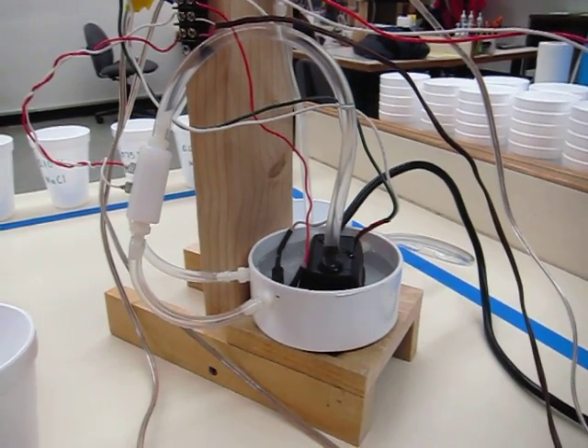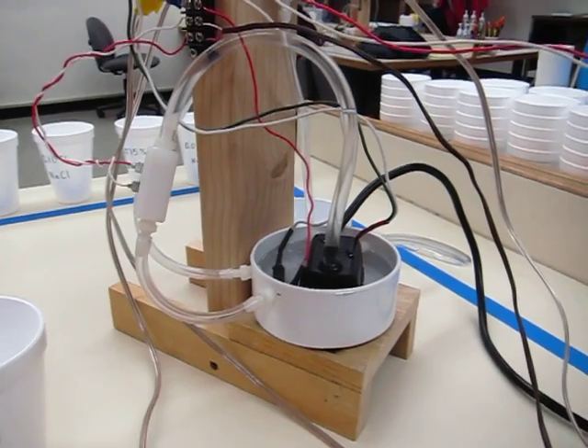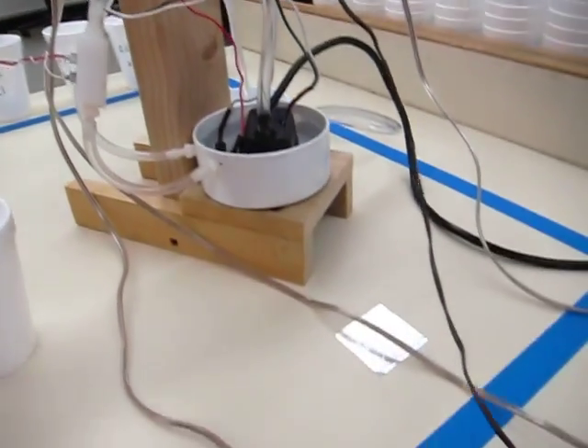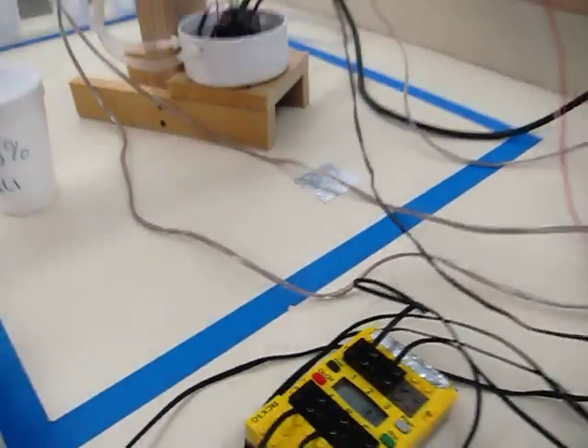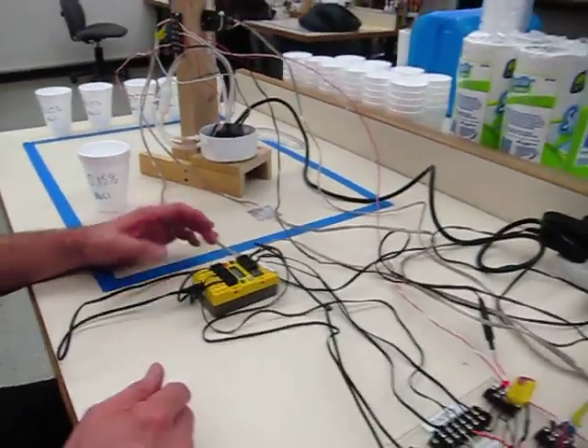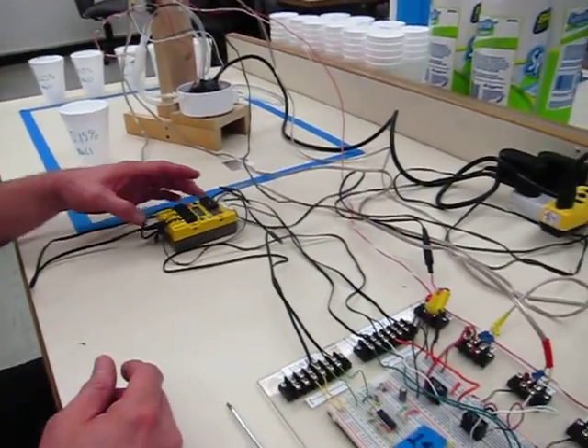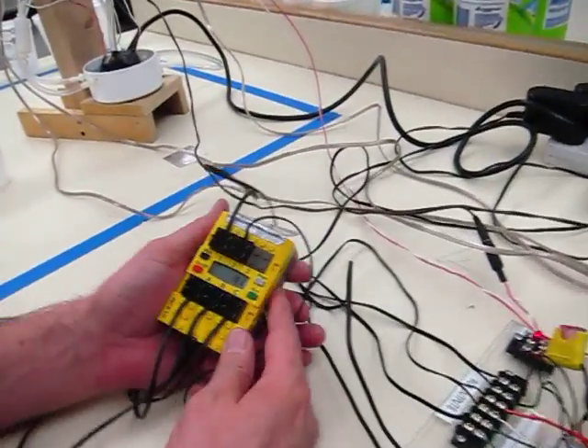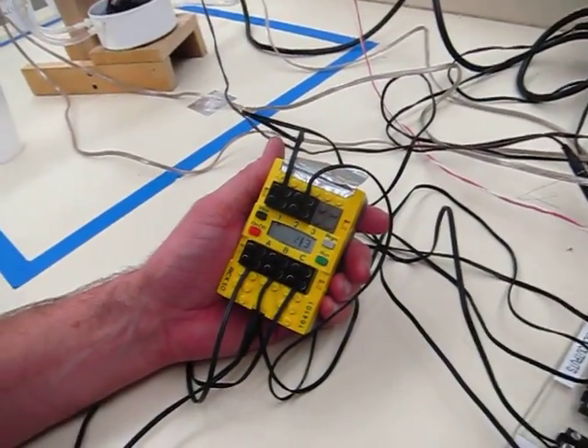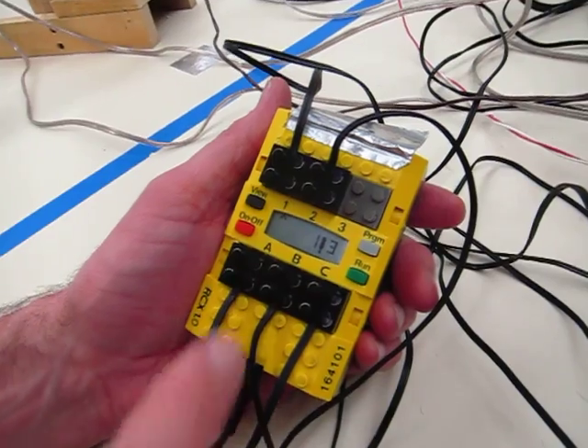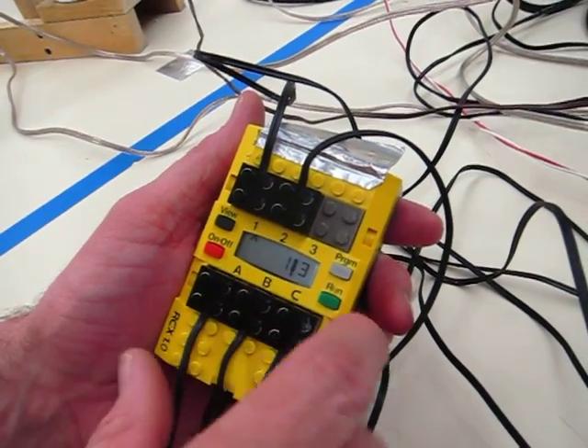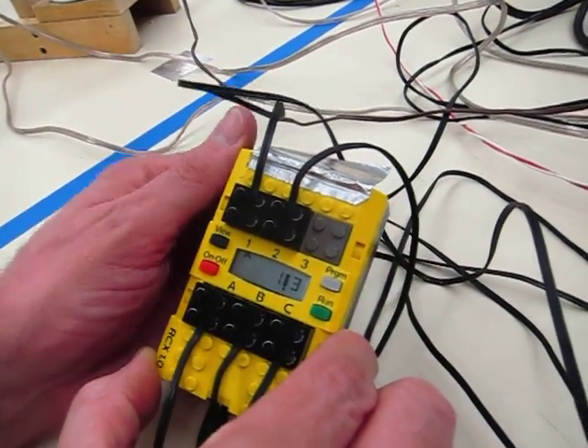All right, so it's recirculating nicely, and the first step in your activities this week is to do a calibration. So this is the 0.15% saline. It's creating a reading right now of 1 or 2. It's varying a little bit. We're reading on sensor 1, and the reading is 1, sometimes 2.